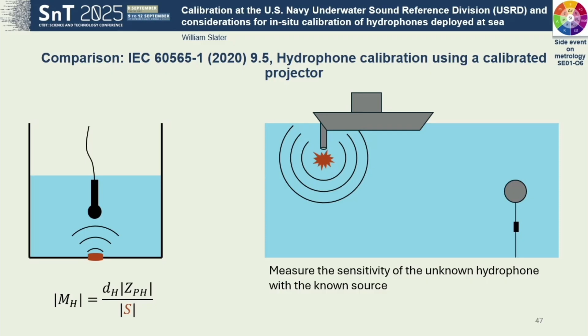Similar to our comparison replacement in the lab, at sea, a source like an air gun could be used along with a reference hydrophone to calibrate an IMS hydrophone. From the language of IEC 60565, this is a projector calibration using a calibrated hydrophone, followed by a hydrophone calibration using a calibrated projector. The repeatability of the source and the accuracy of the separation distance and hydrophone voltage measurements will contribute to uncertainty, as well as additional challenges. For example, correcting for source interference, separating the direct and reflected signals.